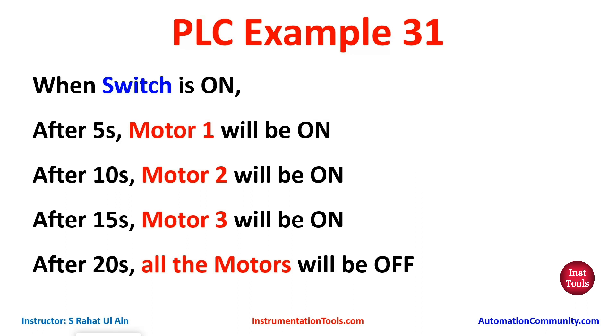After 20 seconds all the motors will be off. For motor 1 to be on after 5 seconds we will use T-ON. For motor 2 and motor 3 to be on after 10 seconds and 15 seconds respectively we will also use T-ON. And then for all the motors to be off after 20 seconds we will use TP. So let's move to EcoStruxure Machine Expert where we will draw a ladder diagram for this example.